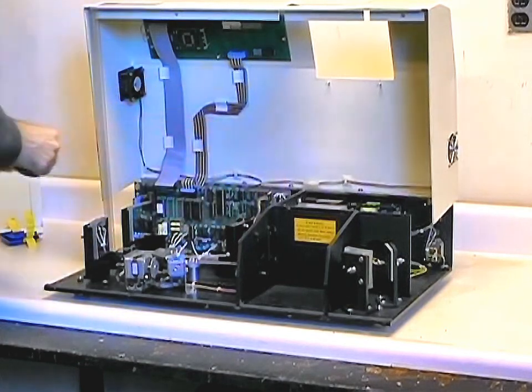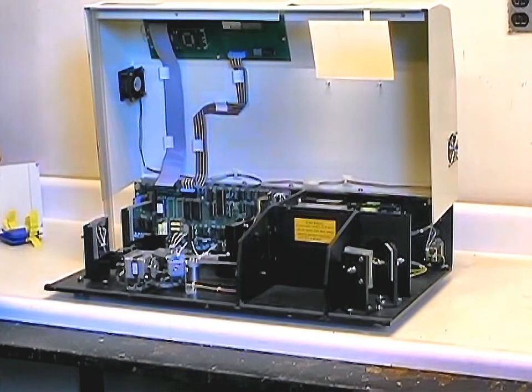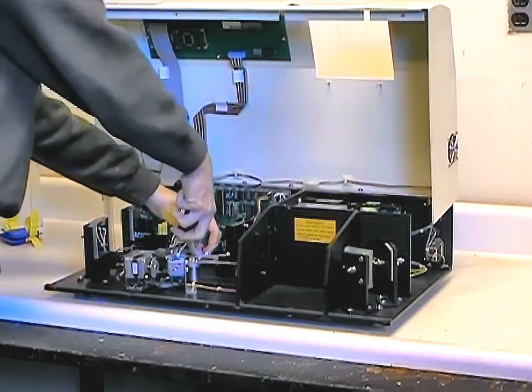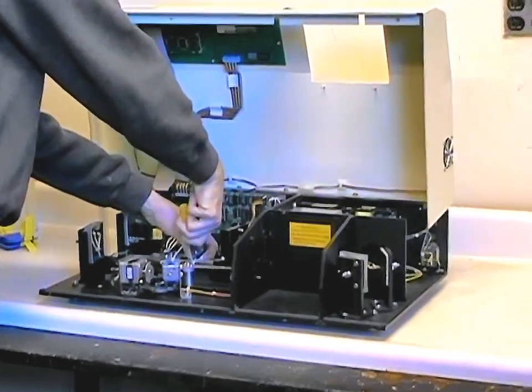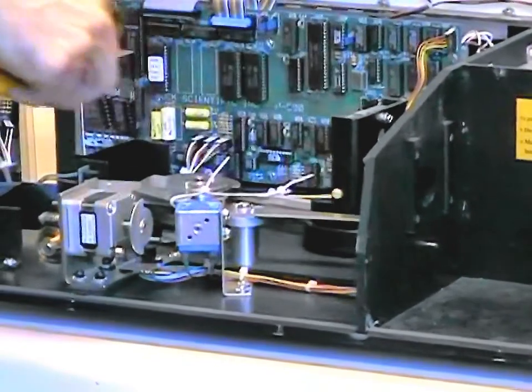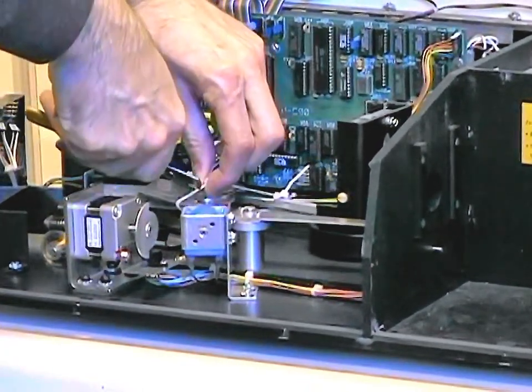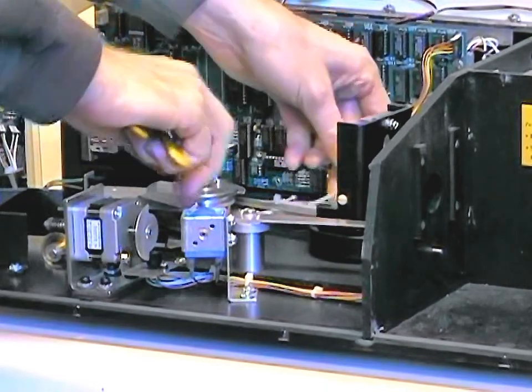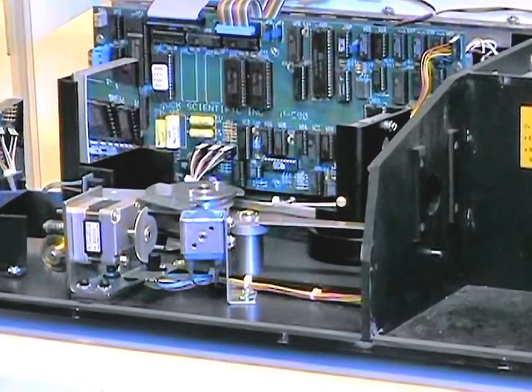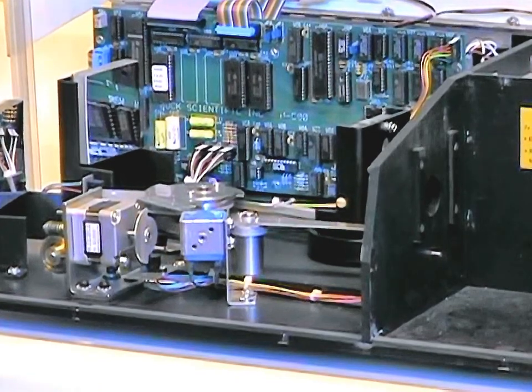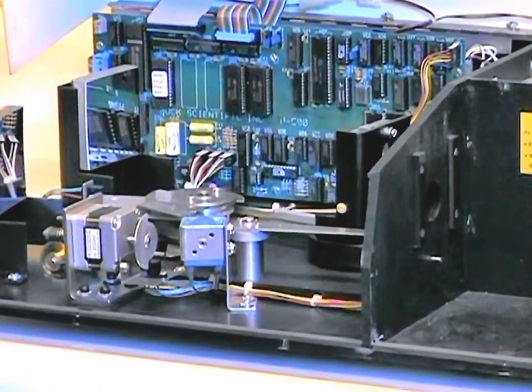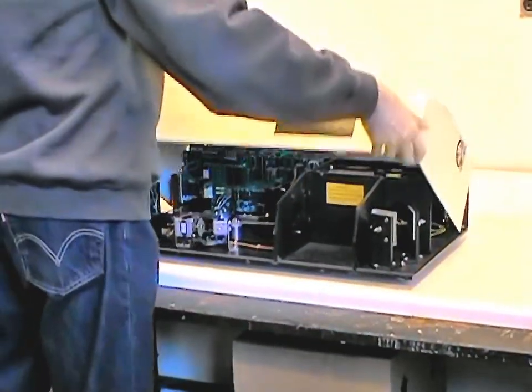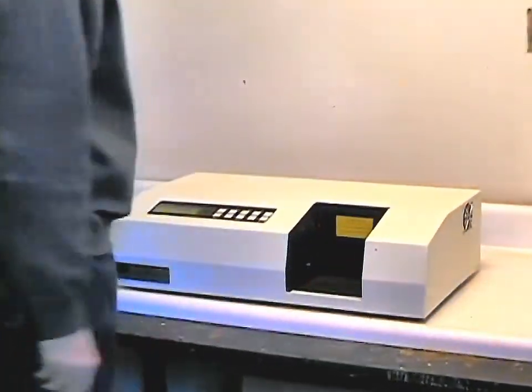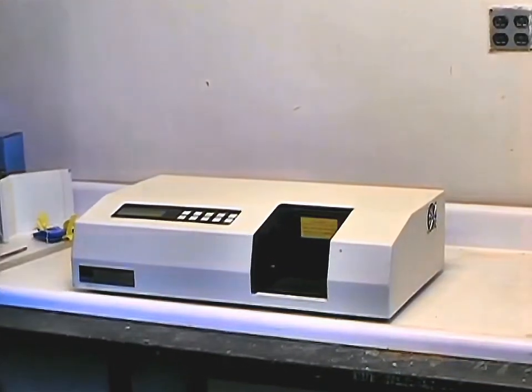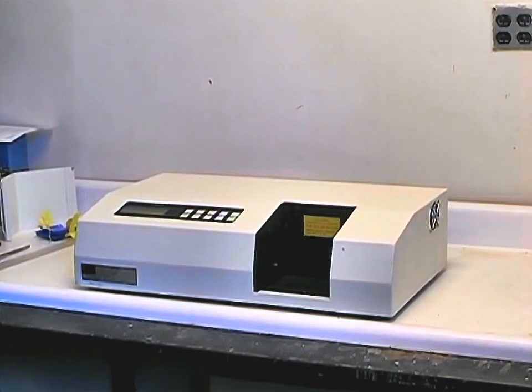Because of some of the spring mounts, try not to move the mirror or diffraction grating, which will offset their positions. Using wire cutters or nippers, you will see a series of cable ties holding the various optical drive arms in place. Carefully cut these. Again, these can be replaced with other devices such as rubber bands or new cable ties if the machine needs to be returned. When this is done, the cover can be closed. And we're ready to plug the instrument in, connect the interface cable, and load the software.